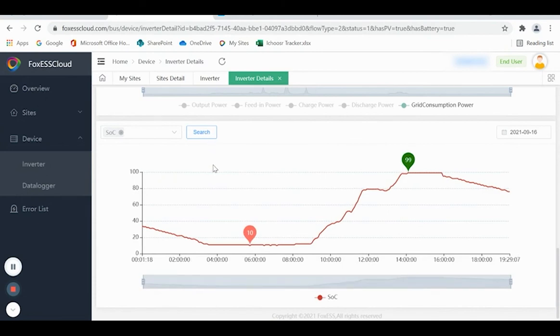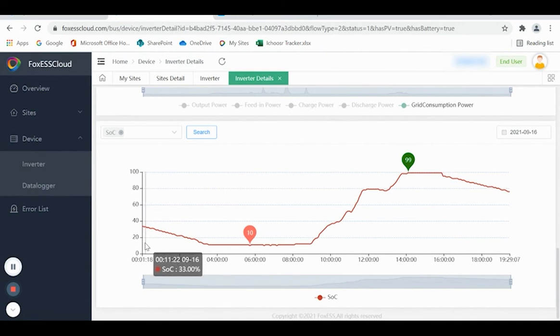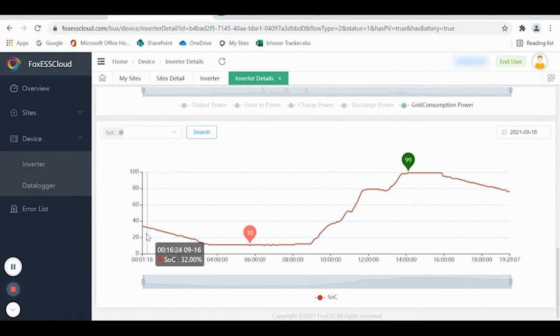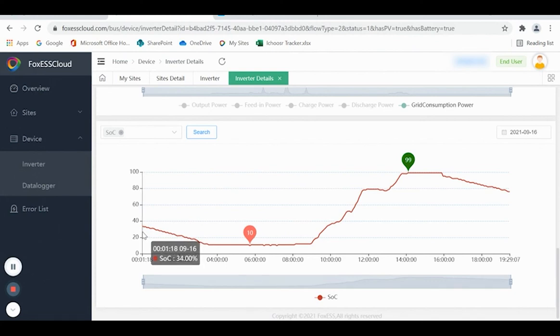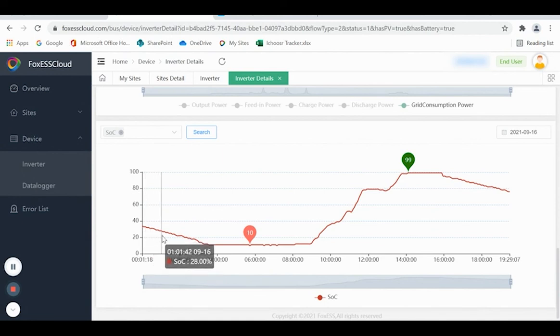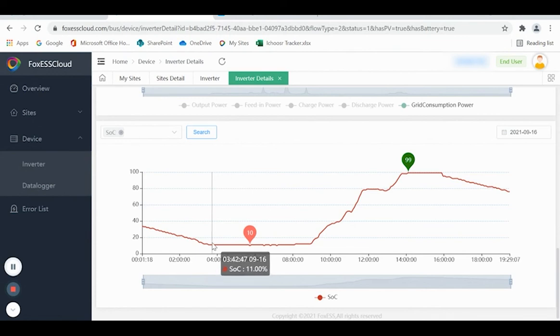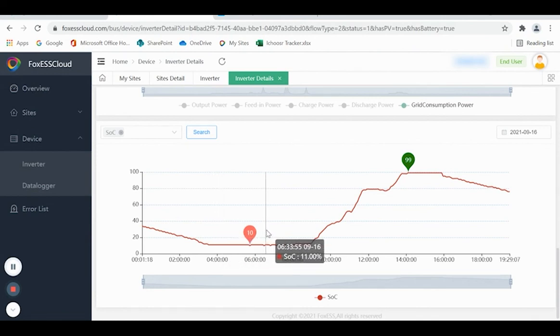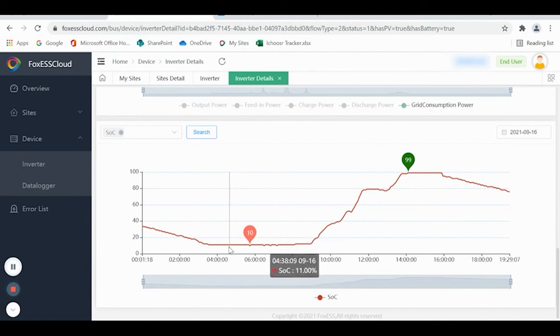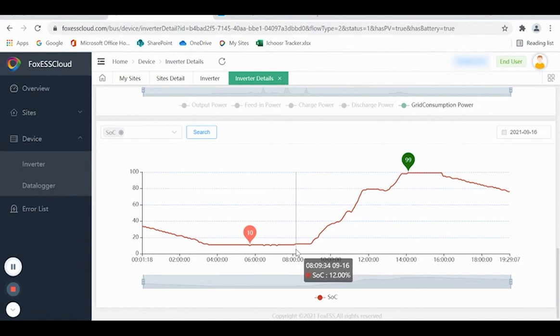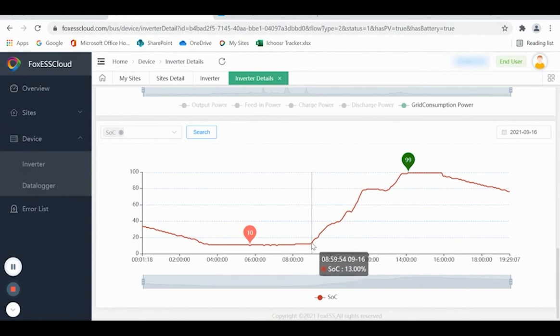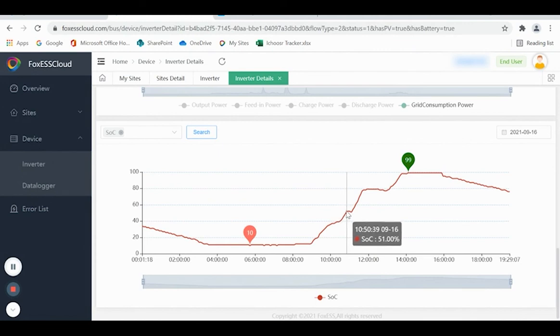It shows you what the battery has done during the previous day. So as you can see on this graph, at midnight there was 34% still in the battery, and this depleted during the early hours until around 4 o'clock when it reached 10%. The batteries need to retain a minimum charge of 10% to stay healthy. Around about 8 o'clock, you can see it started to charge the battery just a little at first, but then this ramps up as the amount of generation from the PV increases.